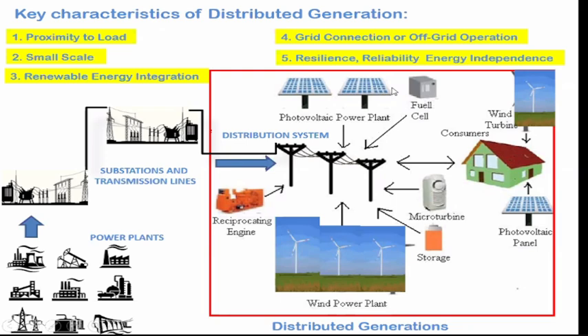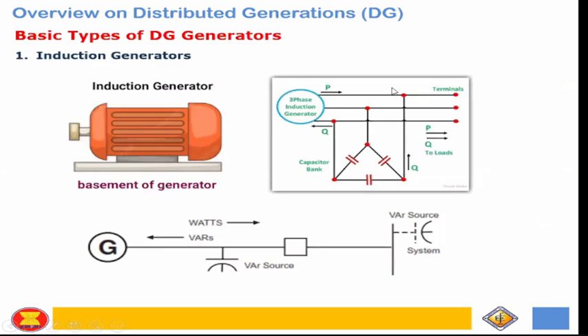DG generators. So first is the induction generators. So induction generators, typically it's less than 500 kVA, no? Yung mga liliit lang na mga generator. Then they start up like a motor with no synchronizing equipment needed. So meaning wala siyang field excitation system. Okay? So it's less costly than the synchronous generator because yung synchronous mayroon siyang excitation system.